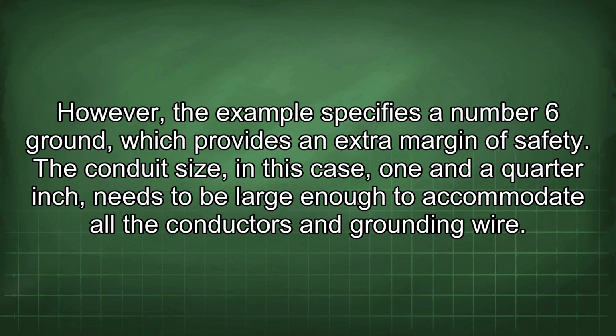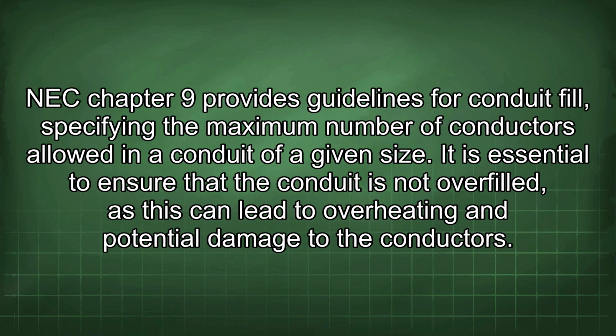The conduit size, in this case 1¼ inch, needs to be large enough to accommodate all the conductors and grounding wire. NEC Chapter 9 provides guidelines for conduit fill, specifying the maximum number of conductors allowed in a conduit of a given size. It is essential to ensure that the conduit is not overfilled, as this can lead to overheating and potential damage to the conductors.